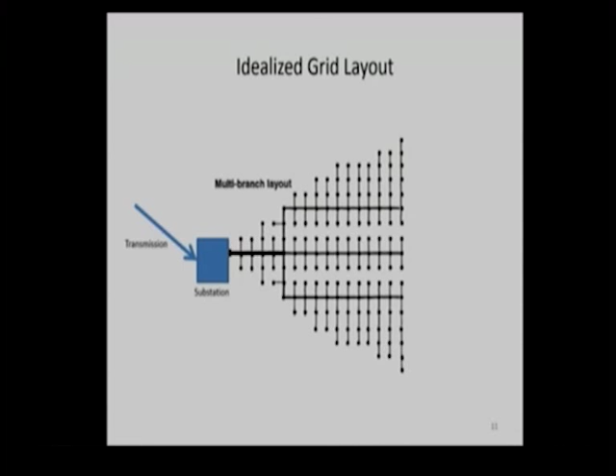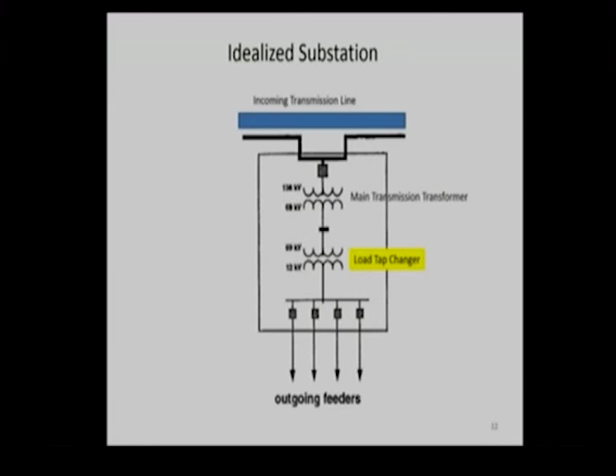The other thing that's important is the substation. And in a substation, you have transmission lines coming in at very high voltage. There's a transmission or a substation transformer that transforms the voltage down through one or more steps to the 12 kilovolts, which is used on the distribution feeder as the main distribution voltage. What I'm showing here is a 2-step process because we do need a substation to have a load tap changer. Sometimes this additional transformer will not be stepping down the voltage as much as I'm showing here. This is just one example. In any case, you have the transmission voltage step down to the main distribution voltage of 12 kilovolts, and that goes out to all the homes and businesses where you have those smaller transformers that take it down to the 120 volt level.